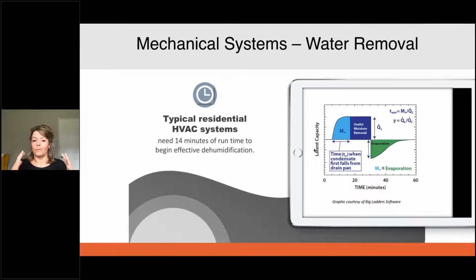And so when someone buys an energy efficient home or a low load home, a high performance home, and their air conditioning starts running for longer periods of time, sometimes they're going to start questioning, did I really get an energy efficient home? Is this right? But we need to educate that, we've sized the system a little bit smaller. It's going to run for a longer period, but you're going to get good dehumidification and moisture control, possibly when there is a sensible load. You always have to have a sensible load in order to dehumidify. So, but we need those longer AC run times in order to actually get water going down the drain.